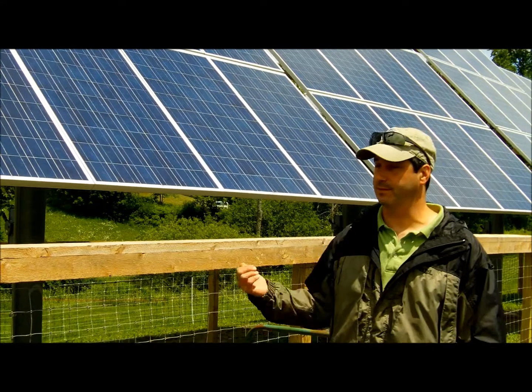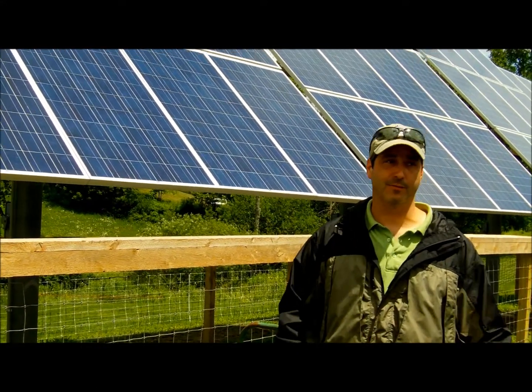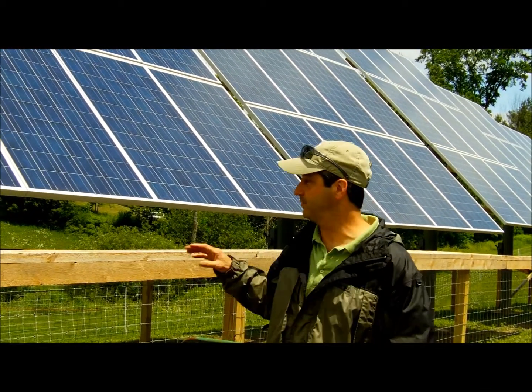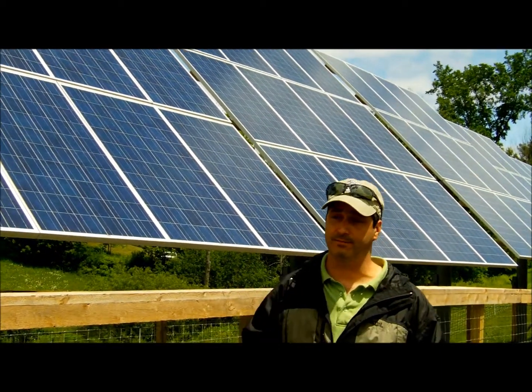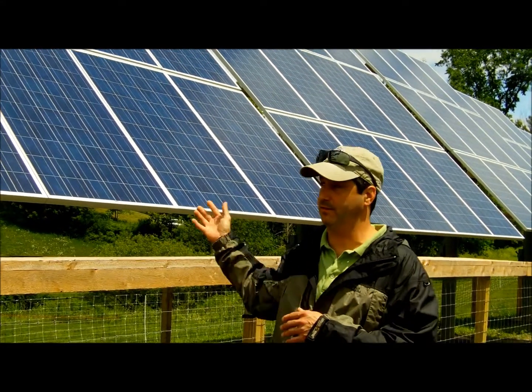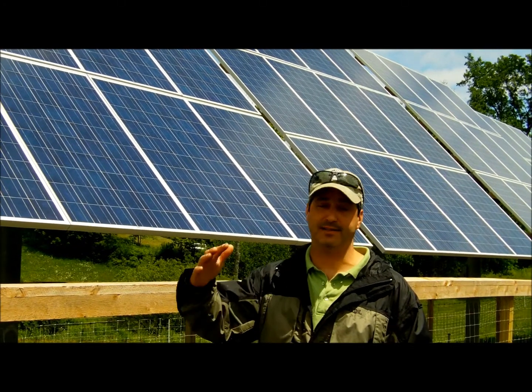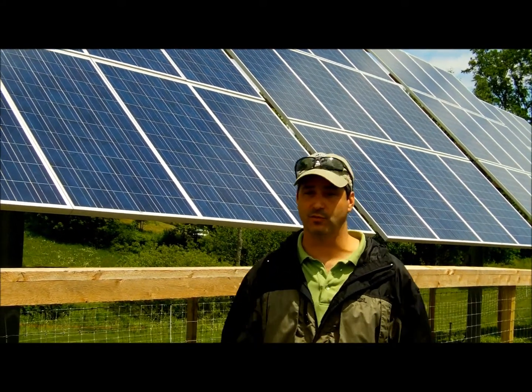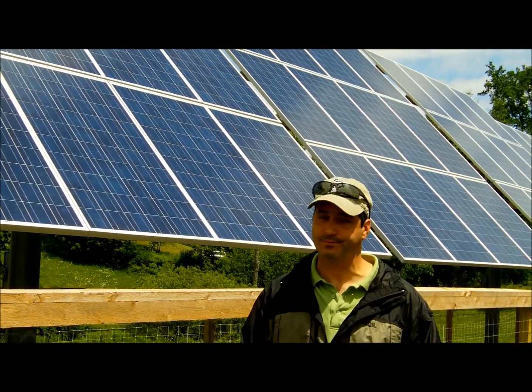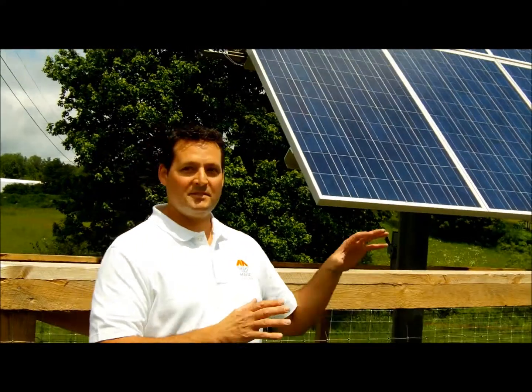Yeah, because when we built this, Mike D'Androni, who worked with Rich to get the material, we were coming out here every day looking at it, because it's like, wow, things are making power. But when you size this, you have to take the coldest recorded temperature in New Hampshire to size the equipment. Because the colder it gets, the more power it produces. And it could max out, and you got to make sure that you size everything to the coldest day that's recorded, which was like minus 40, I think. Yeah, something to that effect. So that's what you got to size the stuff at. At the end of the day, you really don't want to be messing with the solar modules that much.